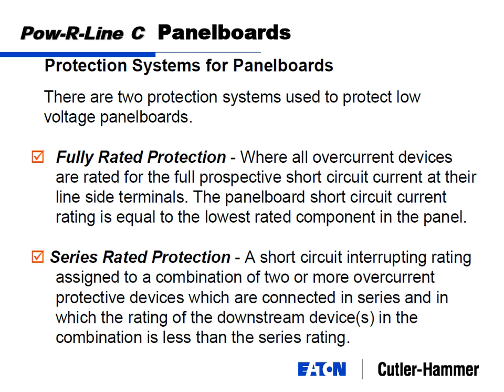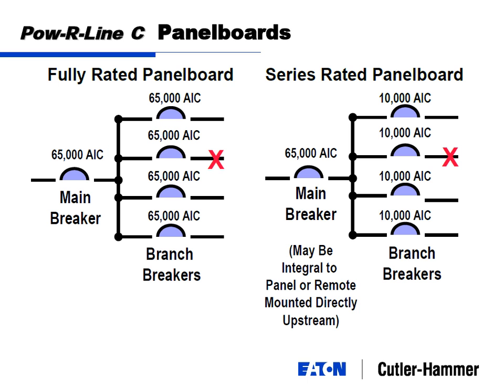these devices here may not all be rated 65,000 amps. I may have to use this type of breaker for my main and this type of breaker for my feeder breaker. Say this is 65,000 amps and this is 10,000 amps, and I looked at which one is going to be the most cost effective. Just by looking at it, you're going to say this one's got to be cheaper. But it doesn't meet the rating. So UL came out with something called a series rating protection scheme.